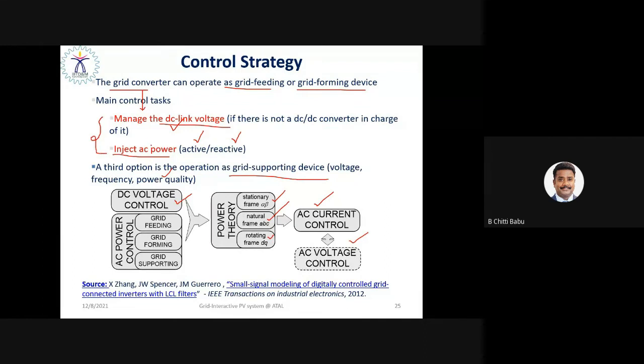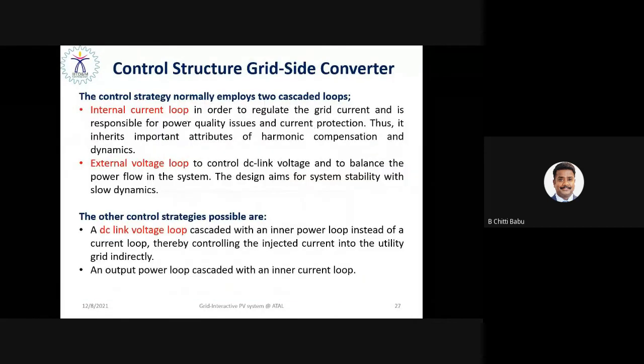So this is basically an inner current control, and this must be an outer voltage control. That is, any control technique employs a cascaded control loop: one is called the internal current control loop and the other the external voltage control loop. The external control loop has to maintain the DC link voltage constant to balance the power flow in the system.